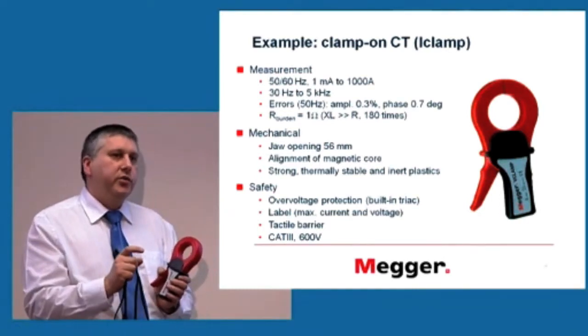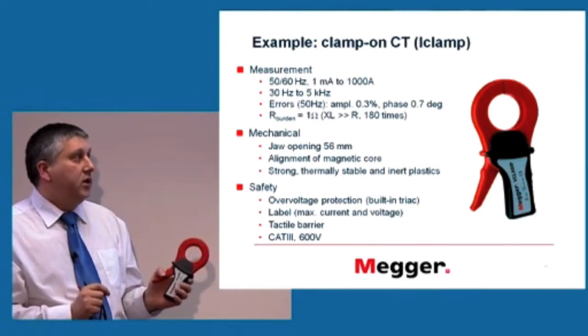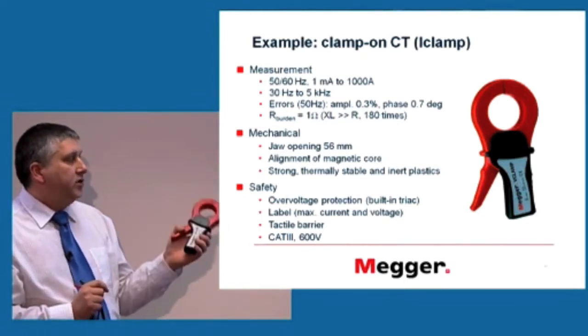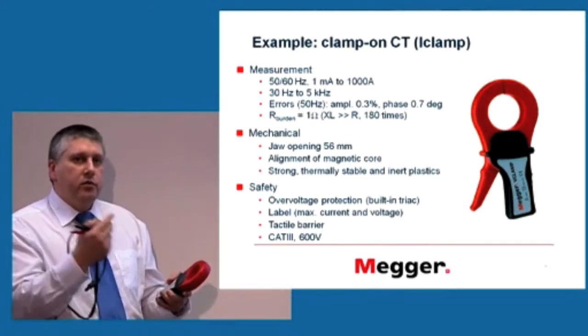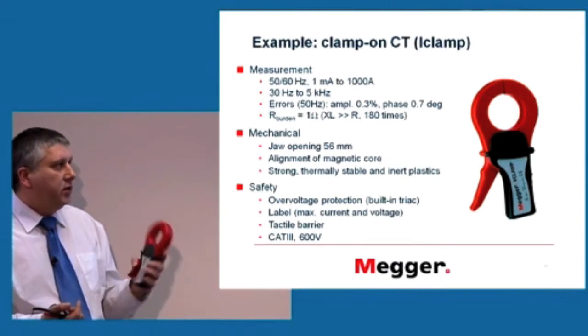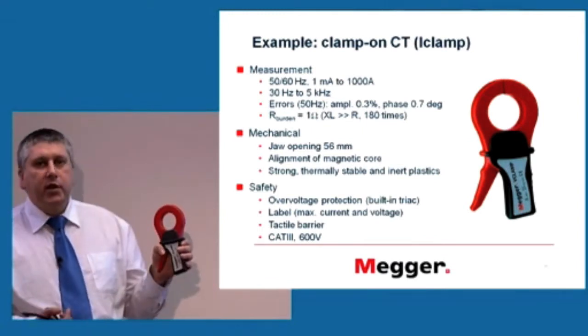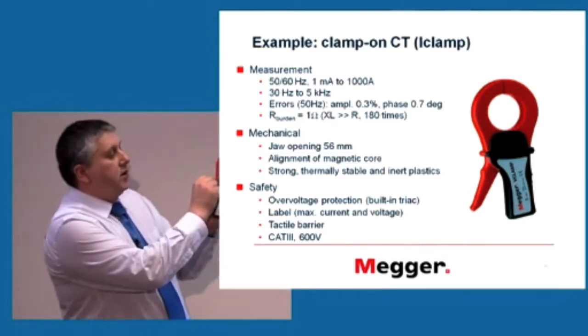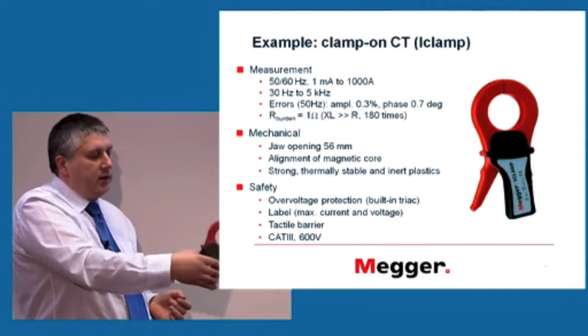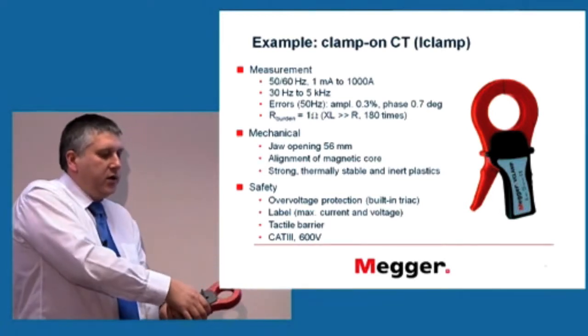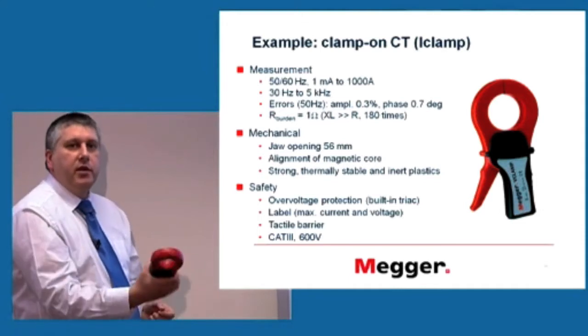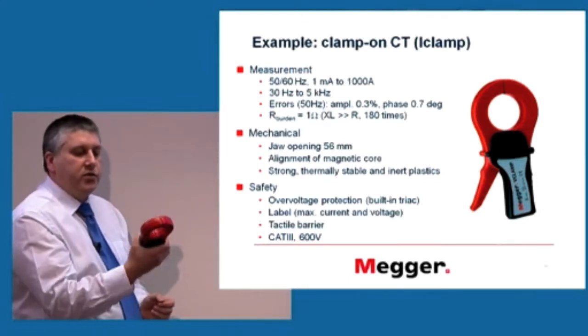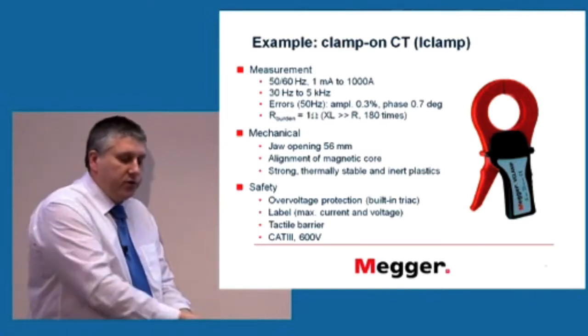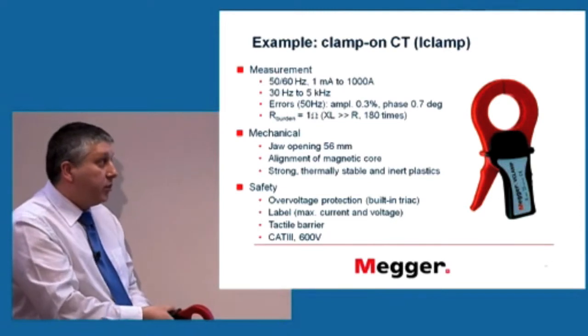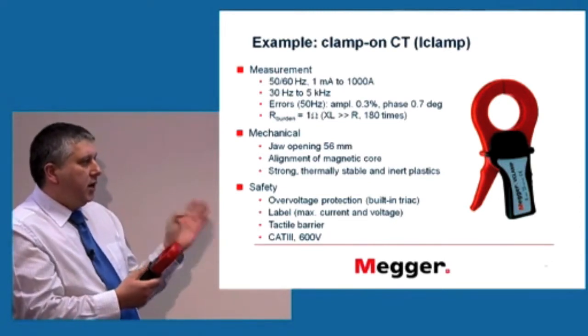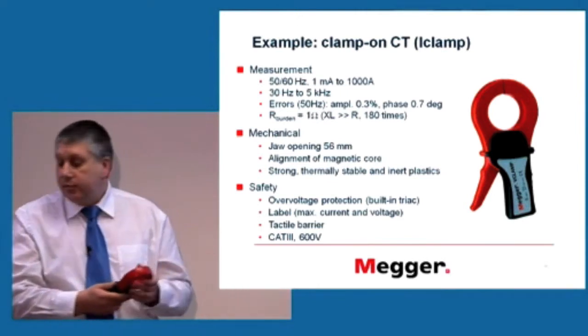So it's perfectly safe for anyone to handle this and clamp around something and not be harmed by the high voltages involved. Obviously, there has to be a label which tells the user what voltages and what currents they can use this part of the device. There has to be a tactile barrier, and the tactile barrier is this bit you can see here. So if I'm handling this device and going into a very tight corner or something, my hand wouldn't slip and go onto the conductor. It has to be very ergonomically designed, so it's easy to open, easy to hold, but also so my hand doesn't slip towards the high voltages possibly. And this device is rated at Cat 3 600 volts, which I will explain in detail exactly what that means.